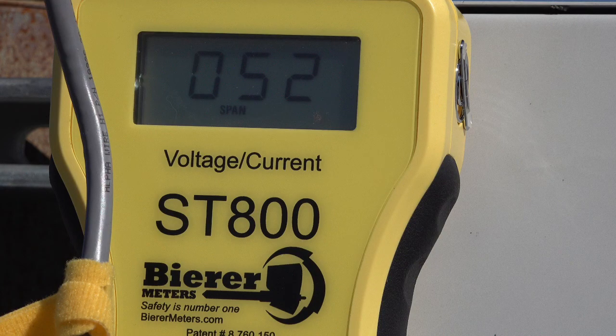Since we were quickly able to determine that both the neutral and the hot on this service are good conductors, now using the count number 52, we're able to compare that with the other hot and the same neutral connection. But first, cycle the ST800 power off. By simply moving the red lead over to the other hot and then turning the ST800 on again and performing the exact same test, we should see an equivalent or close to 52 counts at 800 amps. This would verify that all three conductors are good and this service is then good as well.